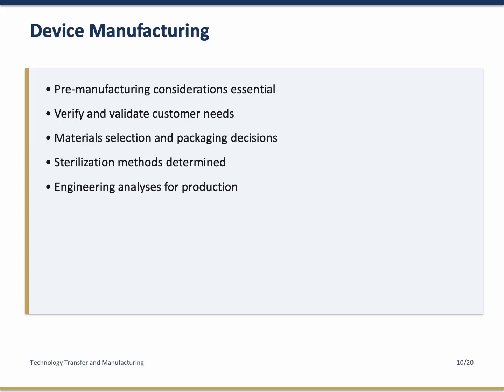Medical device manufacturing requires careful pre-manufacturing considerations before pilot or full-scale production. Customer needs must be verified and validated to ensure the design meets actual requirements. Those needs must be translated into design and performance requirements that manufacturing can achieve.